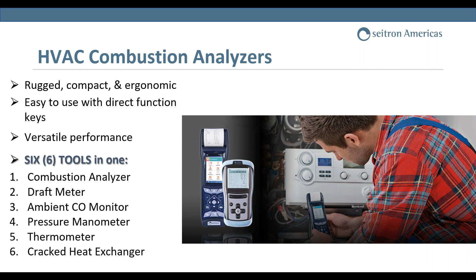But why are analyzers so important, and why are we pushing them so much? Mainly because nowadays, more and more manufacturers on the boiler and furnace side are requiring them. For instance, this is a boiler manufacturer's manual, and you can see clearly that they're starting to put these—and have been for some time now—into the actual manuals themselves, which means it's not really a suggestion, they want it.